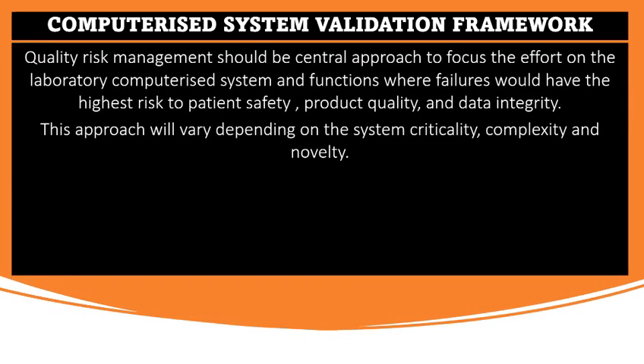The next approach is the computerized system validation framework. While validating the system, quality risk management should be the central approach to focus effort on the laboratory computerized system and its functions, as these have the highest risk to patient safety, product quality, and data integrity. The QRM approach will vary depending upon system criticality, complexity, and novelty. For example, during validation, if you identify any test that fails against the acceptance criteria, you must investigate the root cause of the failure and accordingly take corrective and preventive action to mitigate that risk, ensuring it reaches an acceptable level.